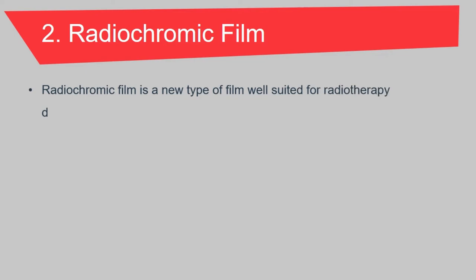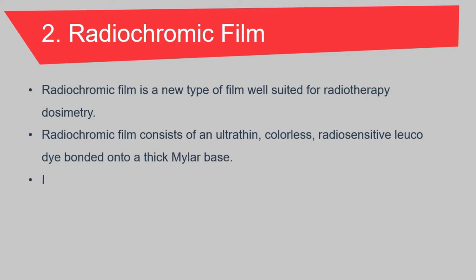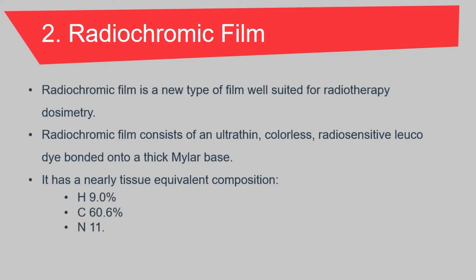Next is radiochromic film. Radiochromic film is a new type of film used for radiotherapy dosimetry. This film consists of an ultra-thin, colorless, and radio-sensitive leuco dye coated onto a thick mylar base. This film has a nearly tissue-equivalent composition, made up of 9% hydrogen, 60.6% carbon, 11.2% nitrogen and 19.2% oxygen.